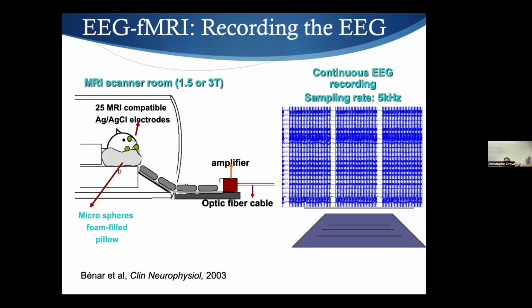We had an issue because that is problematic: some of the most advanced coils that have been developed for fMRI are not developed for EEG. So we had the case where we had to put the wires over the eyes, and I think that's what you've experienced. But ideally, the wires should go out the back.